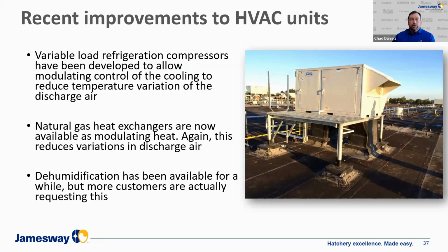And then dehumidification has been available on these rooftop units for a while, and really just in the past few years we're seeing more customers actually requesting this. In a lot of our applications, controlling the room temp is one aspect of it, but keeping the humidity from being too high is also important, even a bit of a luxury with dehumidification on a system like this. But it's very critical in the summer to aid with moisture loss during incubation.